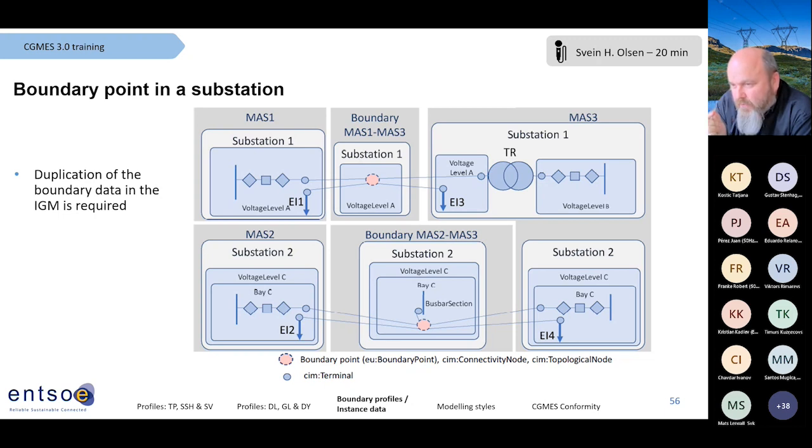And the key then is the value that is in the boundary. Those are the ones that you need to validate the two MAS against. So if there are any differences in those, the tool should report that to be incorrect against the boundary. And then you can also end up with a MAS3, which has a separate substation, and you align these things being matched up, and you go down to where you actually have a bus bar section or whatever the item is considered the boundary being included here. And again, as I said, this becomes more relevant when we are expanding it to deal with system protection schemes, which will need to be duplicated as a minimum between the different actors.